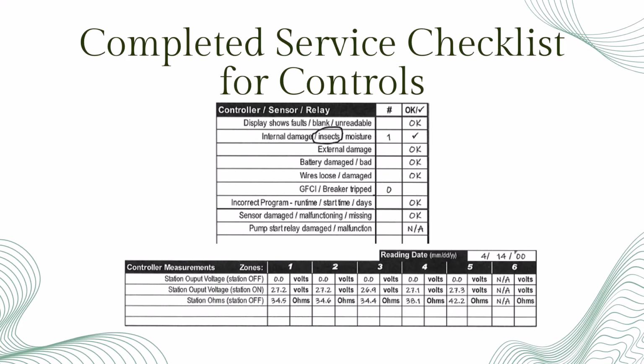For companies that include voltage and resistance testing as part of preventative maintenance, those findings are shown in the second example. None of the stations that were not turned on showed voltage when another station was active, which is exactly what we want to see. The output voltages and resistance readings for each active station were recorded, and the unused terminal, station 6 in this case, was simply marked NA.